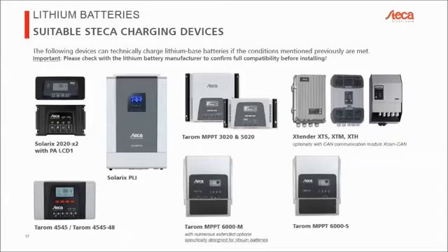One important thing to mention: when buying a lithium battery, make sure it does not need to communicate to the outside. Some batteries, for example, have CAN communication and will only function if you communicate with them regularly—if you don't, they shut off after several seconds or minutes. So because all except the Xtender do not have CAN communication among our devices, these types of batteries would not be suitable for use in an off-grid system.